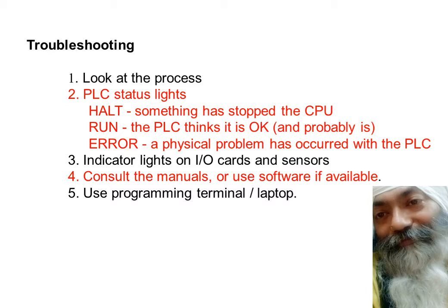What you can do is use the programming terminal or the laptop as a programming terminal to get into the PLC, and there's something called force functions. Force functions are where the actual output is not given by the program, but you want to check whether the actuator is working properly or not. So you can force that output on to check the actuator.